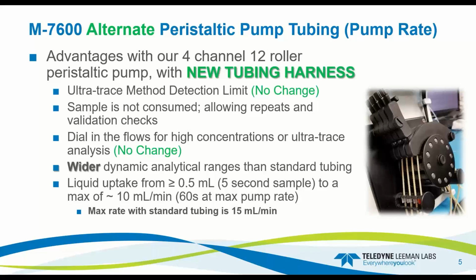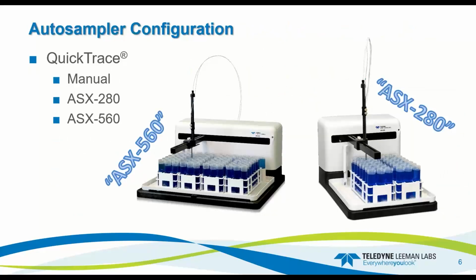You can dial in the flows for higher ultratrace concentration. That's also, there's no change there. We do have a wider dynamic analytical range, as I stated earlier, than the standard tubing. Liquid uptake is still as little as approximately 1/2 ml. That's 5 seconds of dip into the sample tube with the probe, to a max of 10 mL per minute, and that's at 60 seconds at max pump rate. The max pump rate for the standard tubing was about 15 mL per minute.